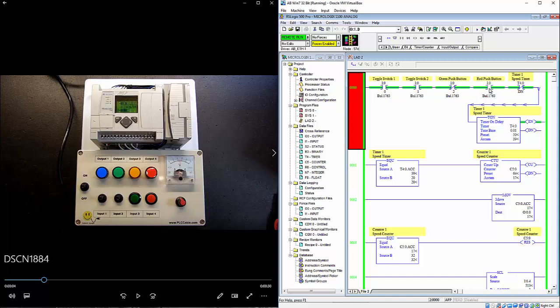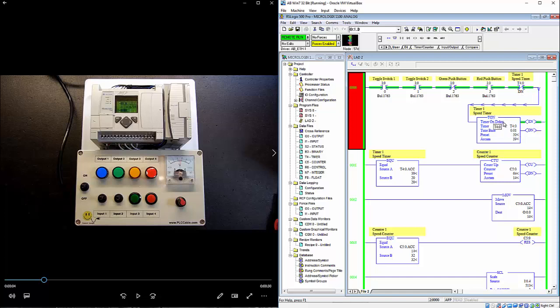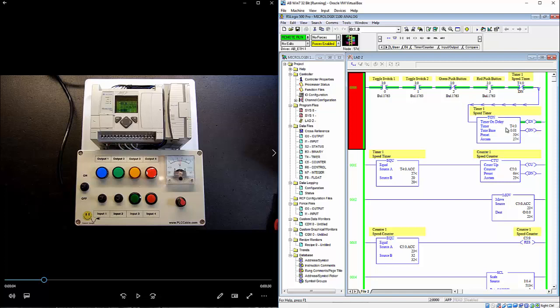So when we flip up both toggle switches and they're both enabled, neither push button is pushed. Then we have our timer, which is T40. And basically what this is doing is it's actually so fast you can't see it. But when T40 hits 50, when the accumulative hits 50, this done bit is true. And what that does is it opens up the logic, it opens up the logic and the timer restarts itself. So this is basically just running in a loop. So as long as nothing's doing, then it's just going to be going over and over counting to 50.